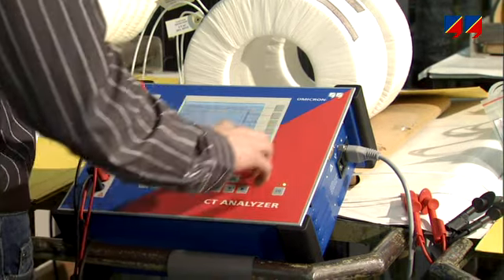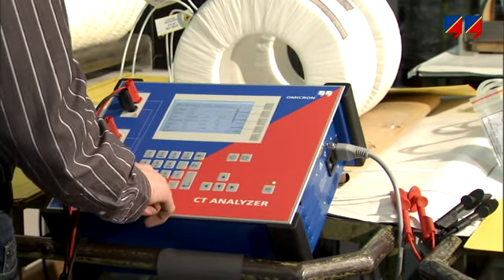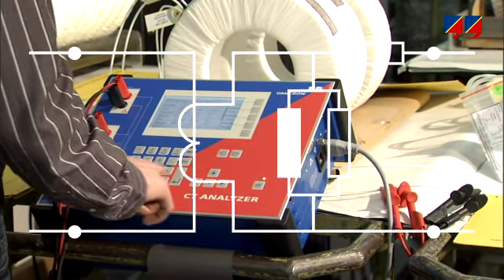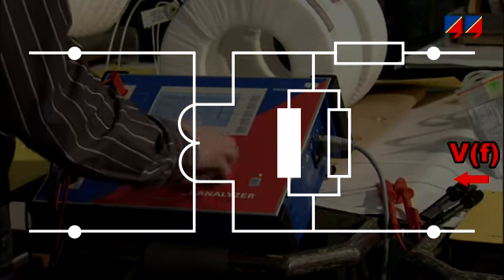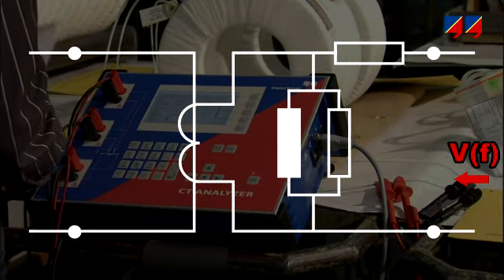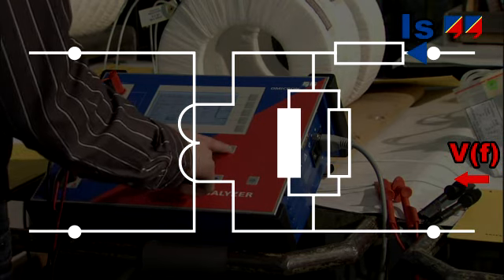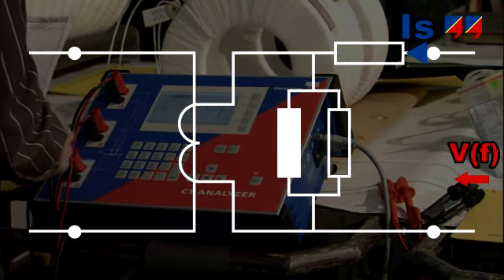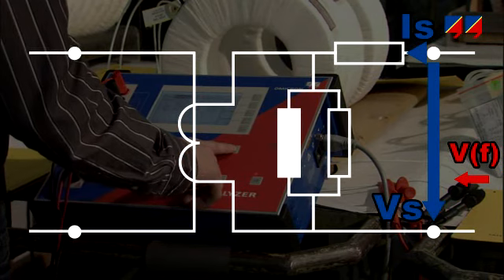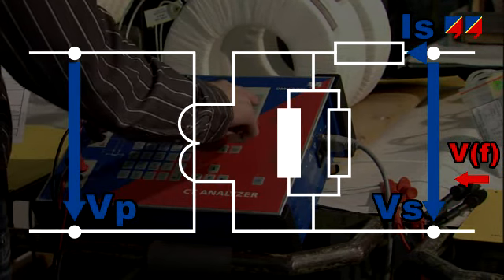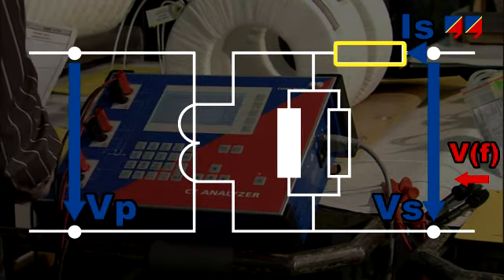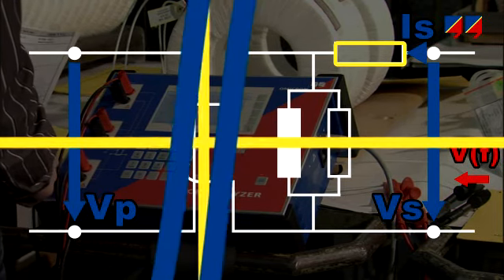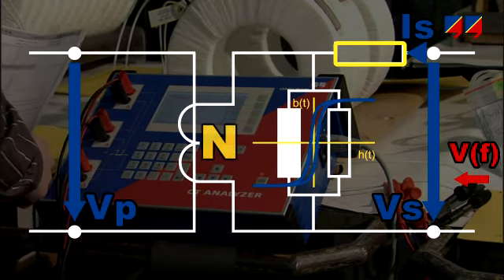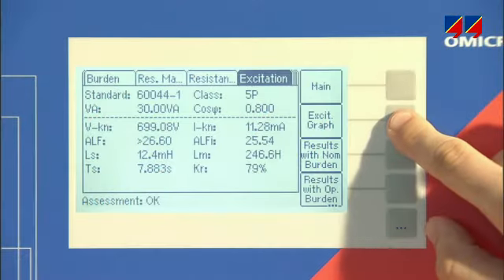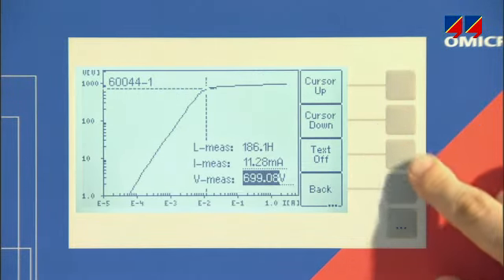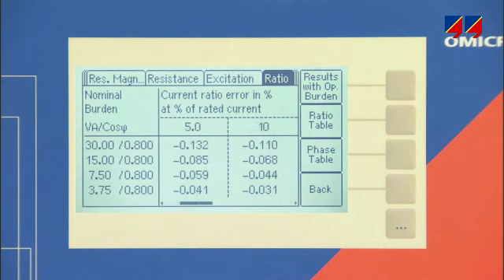CT Analyzer determines all of the relevant parameters of a CT during a test run of typically 1 minute. It injects a variable frequency signal into the secondary side of the CT and measures the current injected into the secondary terminals and the corresponding voltage applied, as well as the voltage induced on the primary side. It measures the DC winding resistance, the excitation curve, and the turns ratio, determines all the parameters of the CT model, and displays the accuracy data for all current and burden values.